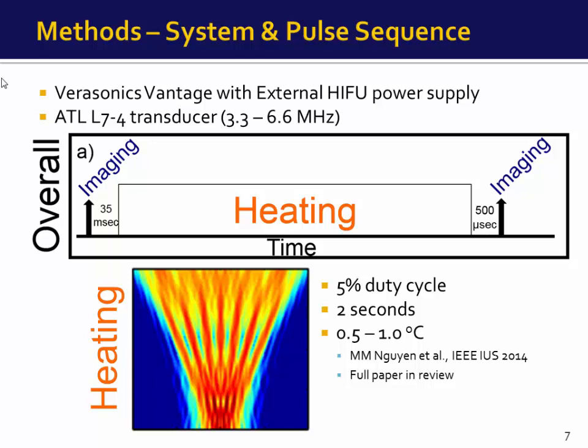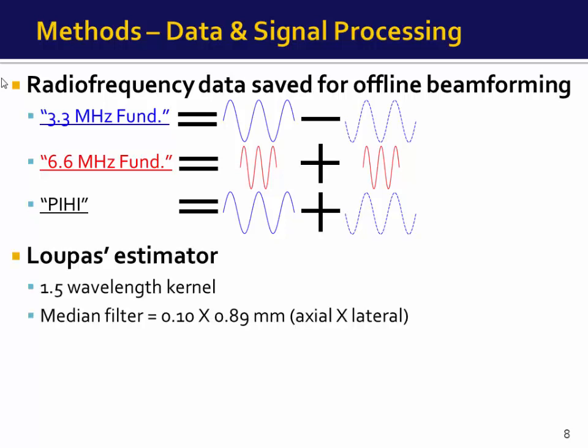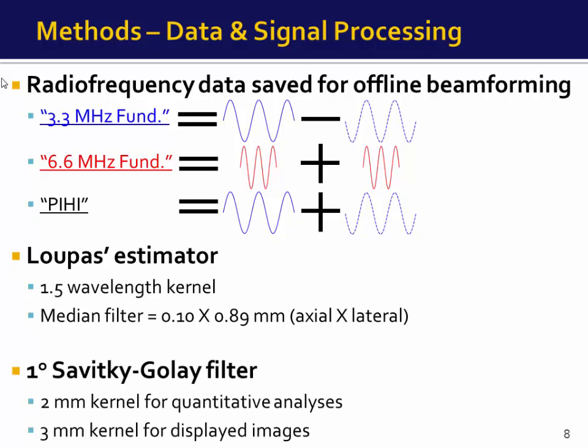The heating beam was driven at a five percent duty cycle over two seconds, resulting in a temperature rise of 0.5 to 1 degree Celsius. RF data was saved for offline beamforming. The 3.3 MHz data was the difference between the two phase-inverted 3.3 MHz signals, the 6.6 MHz data was the sum of the two in-phase 6.6 MHz signals, and the pulse inversion data was the sum of the two phase-inverted 3.3 MHz signals. We used Loupas's estimator to track displacement with a 1.5 wavelength kernel.